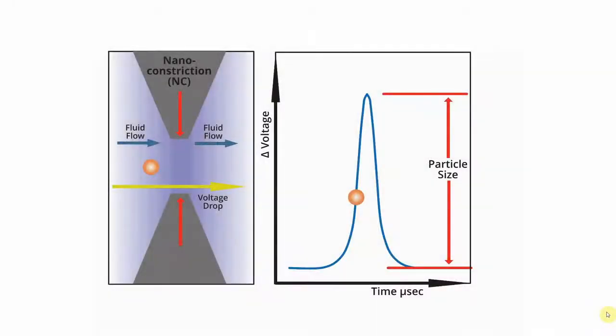As the particles transit the nanoconstriction, they create a change in electrical signal that's directly proportional to the volume of the particle, regardless of its shape and regardless of the material it's made of.